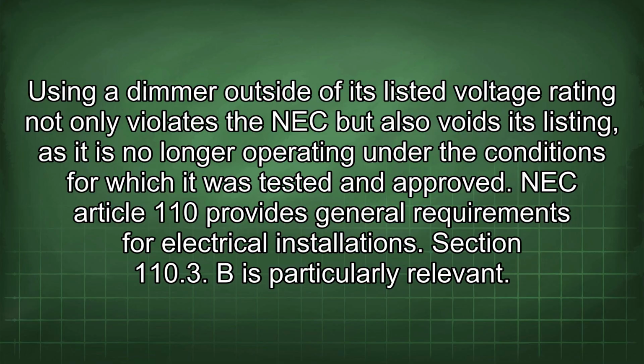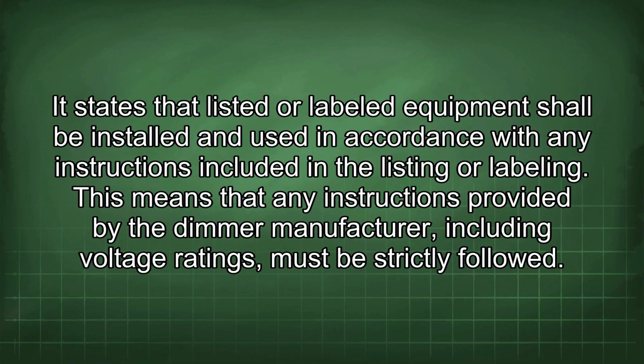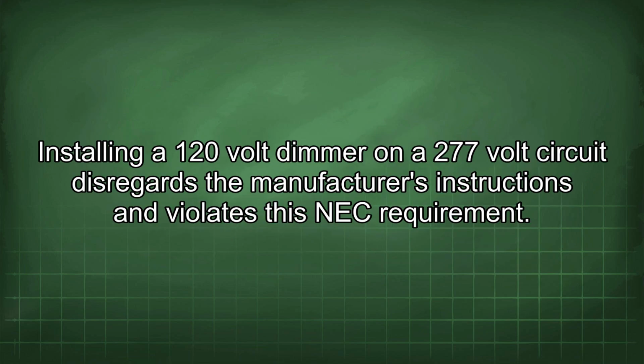NEC Article 110 provides general requirements for electrical installations. Section 110.3(B) is particularly relevant. It states that listed or labeled equipment shall be installed and used in accordance with any instructions included in a listing or labeling. This means that any instructions provided by the dimmer manufacturer, including voltage ratings, must be strictly followed. Installing a 120-volt dimmer on a 277-volt circuit disregards the manufacturer's instructions and violates this NEC requirement.